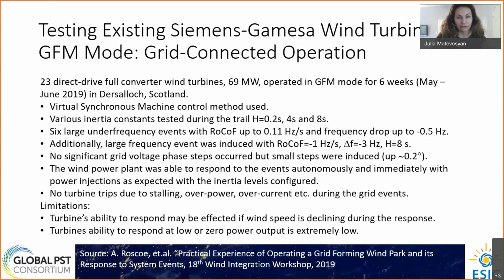There were 6 large under-frequency events during the trial that naturally happened on the system, with the largest rate of change of frequency 0.11 hertz per second, and the largest frequency drop down to 0.5 hertz, the delta F being 0.5 hertz. Additionally, a large frequency event has been induced and tested with an inertia constant of 8 seconds, and all responses that they got during the test were as expected for the inertia constant set.